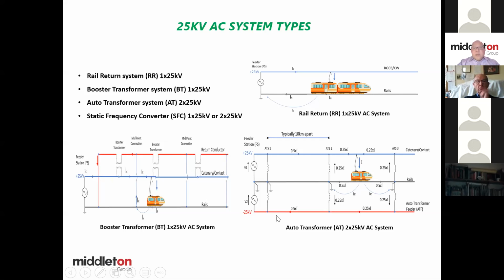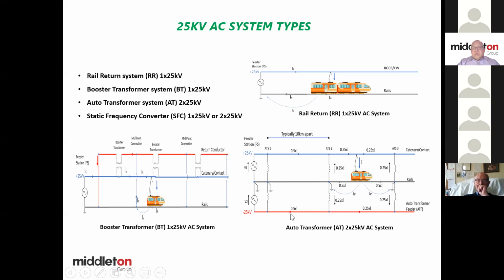So, and of course, if you have booster transformer failure, it will give you very poor performance in the electromagnetic field cancellation. The idea is that you've got the return conductor very close to the contact wire to cancel the magnetic field. But if you have a booster transformer outage, that benefit is reduced or is not there. And of course, the auto transformer system was introduced.